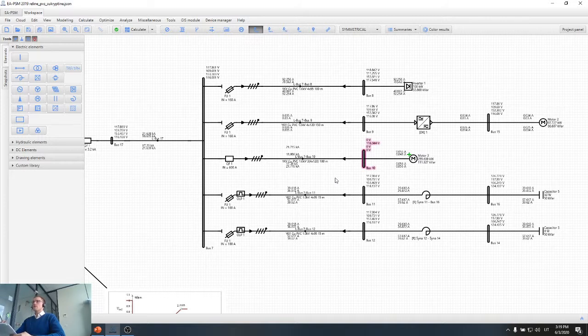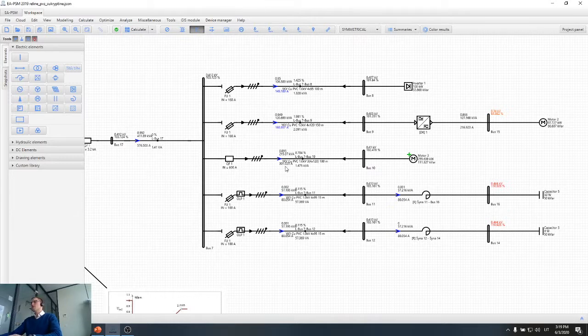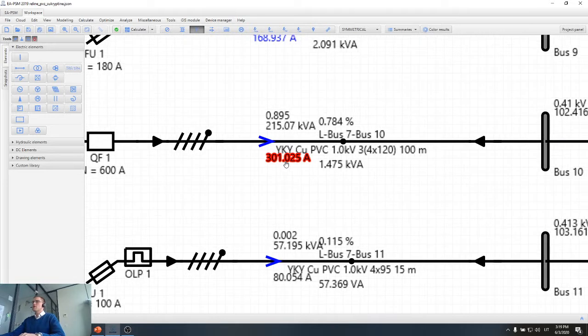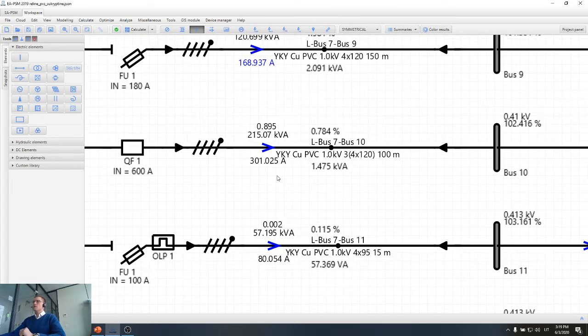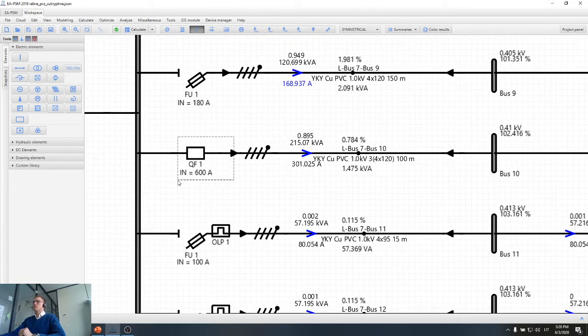So now, what are the calculations that we need for short circuit and for protection coordination? I will quickly look through the list of those calculations. First of all, it is power flows. When we calculate power flows, we get very important information for protection coordination, which is the nominal current, or normal current, in the electrical network during normal mode of operation. For example, for this motor, the normal current is 301 amps. So we must ensure that our protection device nominal current will be bigger than this normal current, and that the pickup current for this protection device will also be bigger.